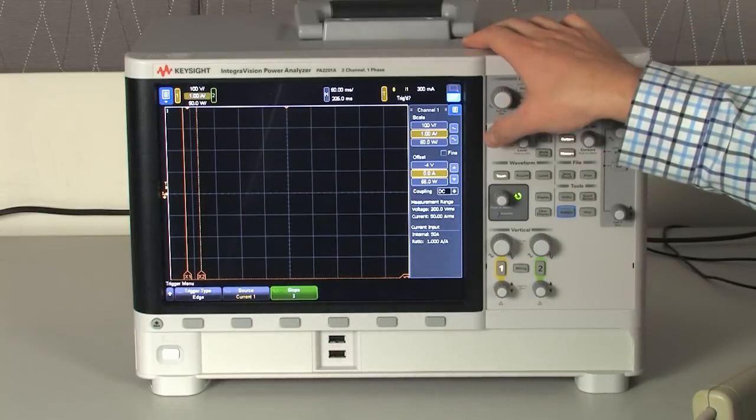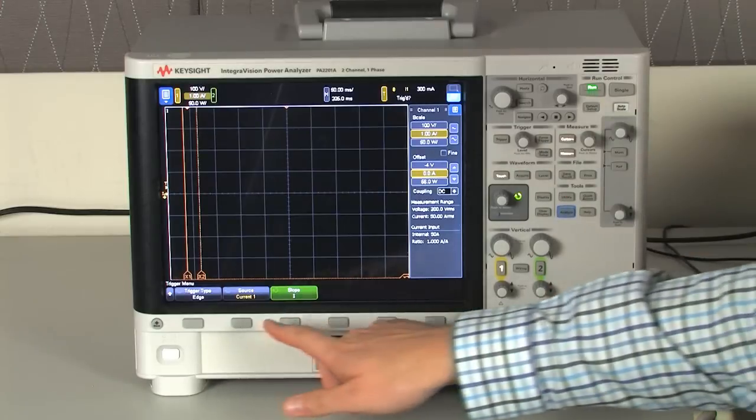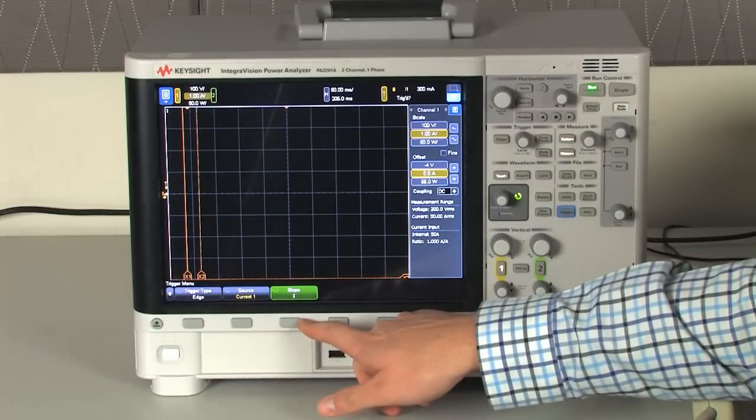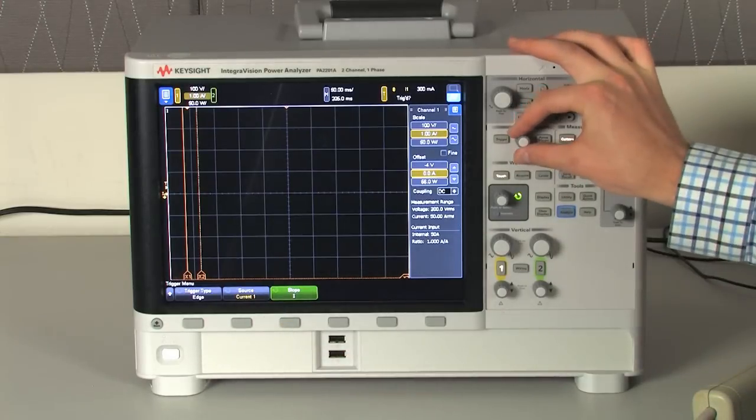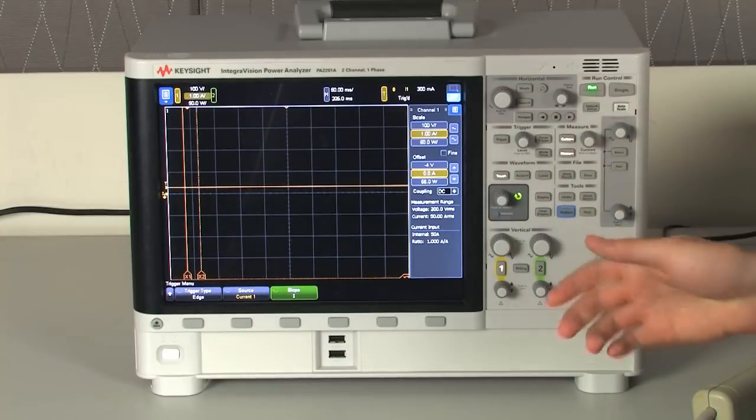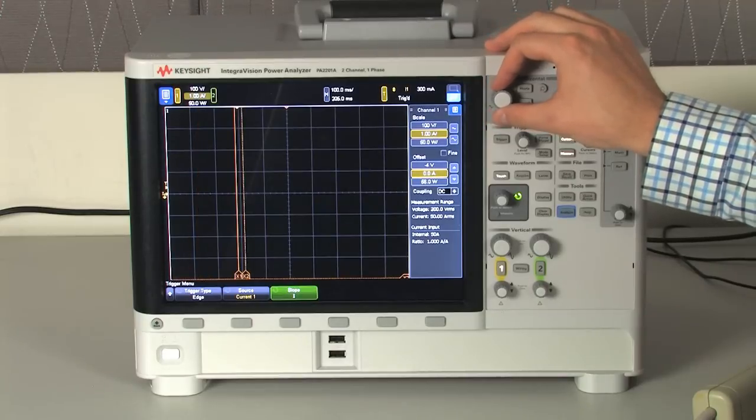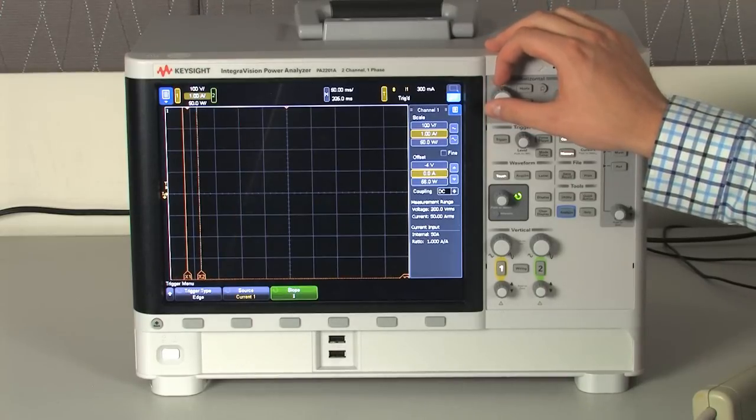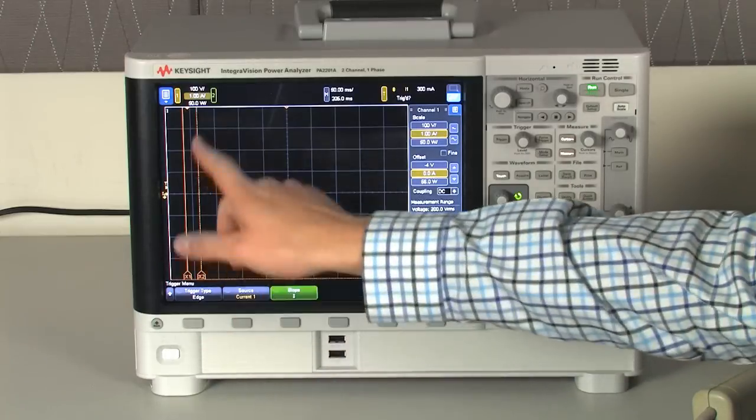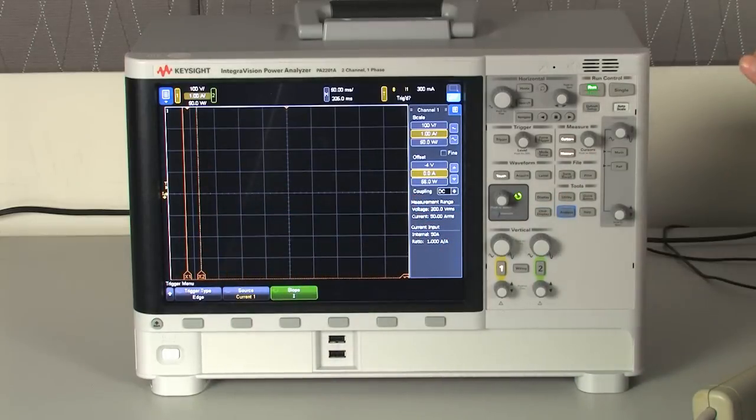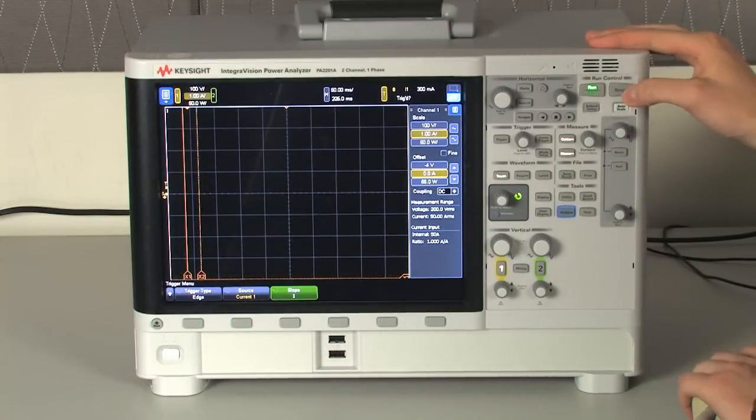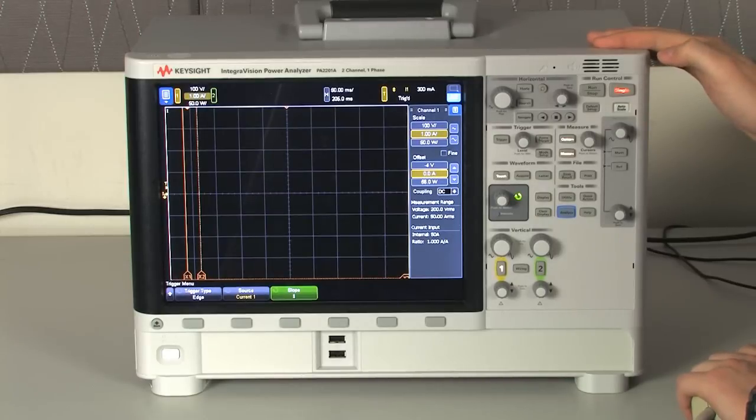The next thing is I want to change the trigger to be triggering on current 1. I'm just going to change the slope to any and set the trigger level to a level that will appropriately trigger for this application. The other thing is I adjusted the horizontal scale to be a little bit larger so I can easily capture the inrush current plus the steady state. So now I'm going to start single shot mode and see if we can capture it.